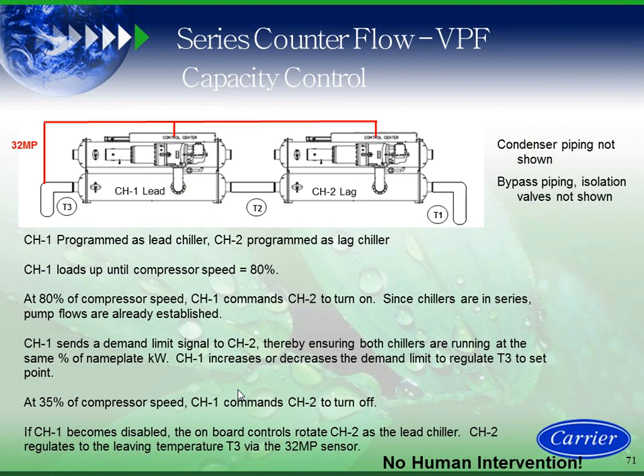Chiller 1 would load up to approximately around 80% compressor speed. And unlike the centrifugal, speed equals load. Okay, so at 80% speed, chiller 1 will command chiller 2 to turn on. They will both be operating off of a common leaving water sensor. And then chiller 1 will make sure that we're optimized. And then when we turn off, we're going to be at 35% compressor speed. Then chiller 1 will command chiller 2 to turn off. Okay, so that's basically the controls of the machine itself.